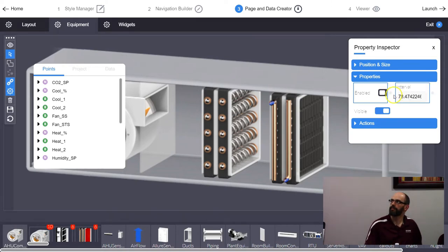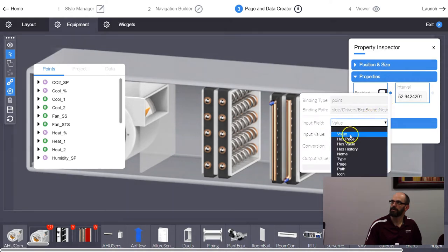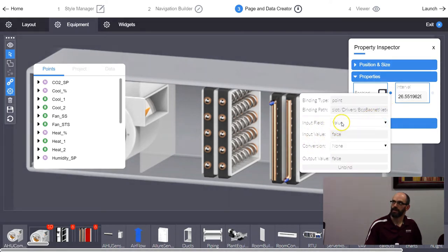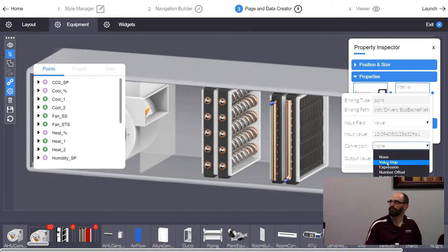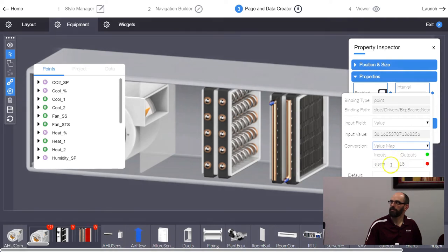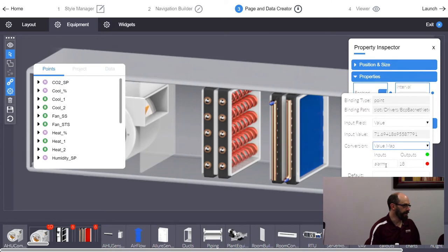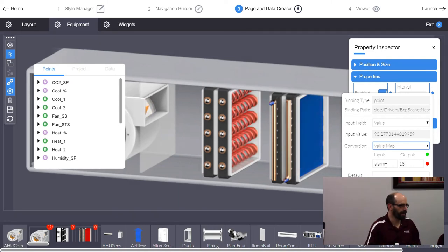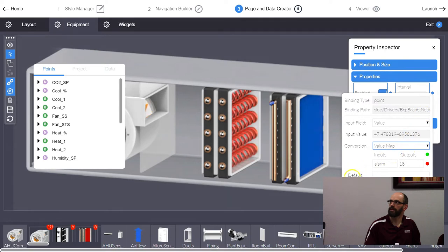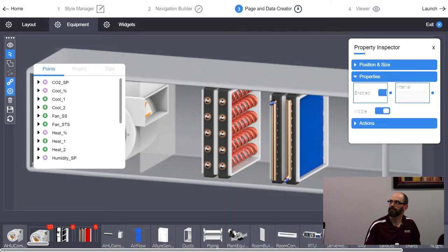You could use percentage on coils — that's possible with some dynamic linking. Inside the gear settings you can create a value map: when the value comes in as 15, make it On; 16, make it Off. Or set ranges. A lot of the logic that used to take a while in AX can be done right on the point here. You can also do a number scale — Input 0 equals 100, Input 100 equals 0 — to reverse the value for things like fan speed animation direction.